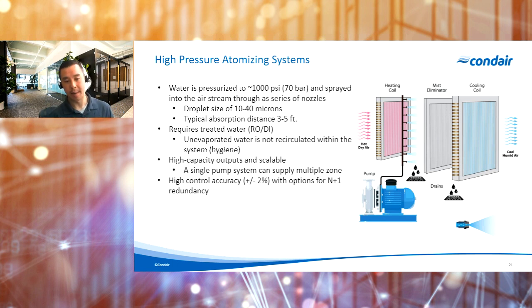So as I mentioned, with this system, we do need treated water. So that's either reverse osmosis or deionized. Really, the main requirement there is to ensure that any minerals that are in that water that we're spraying do not precipitate out as a dust as those droplets are being evaporated. Those can potentially clog the mist eliminators. They can potentially make their way downstream into the space. And then it's also important to have the treated water to ensure that we're not clogging those nozzles. Because we're spraying that water through a very, very fine orifice, any type of clogging can cause issues with dripping or clog the nozzles themselves.